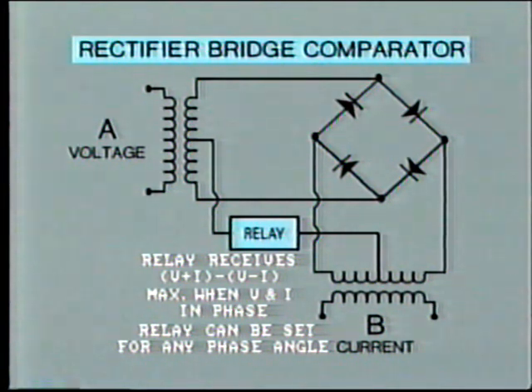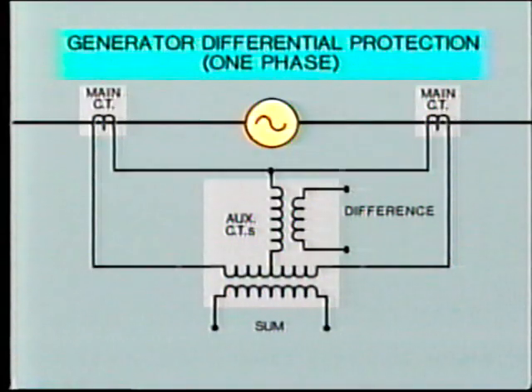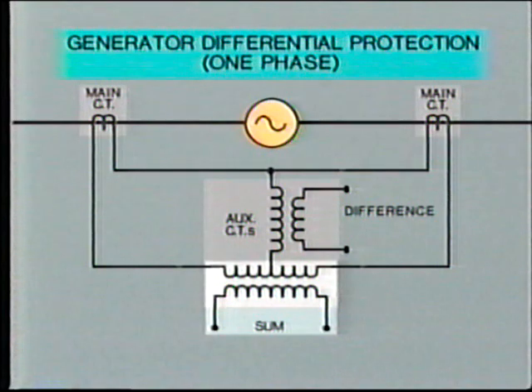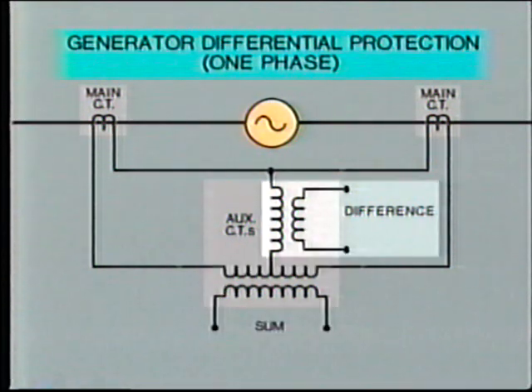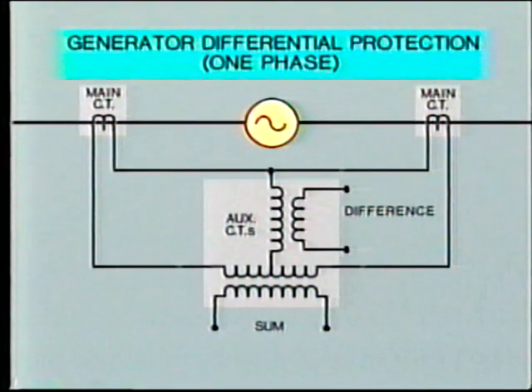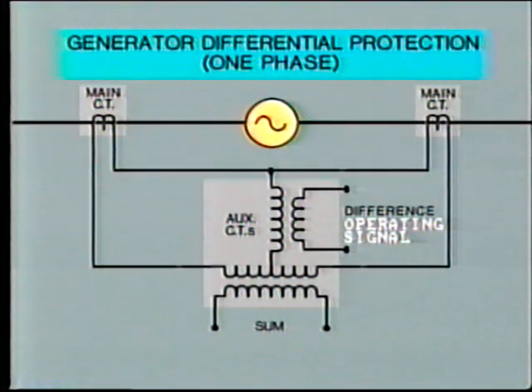This type of relay is also used in generator differential protection. Let's take a look at this. This diagram shows the CT connections for one phase only. This auxiliary CT vectorially summates the CT currents, while this one vectorially measures the difference. The voltage difference becomes the operating signal, while the voltage sum acts as the restraining signal.